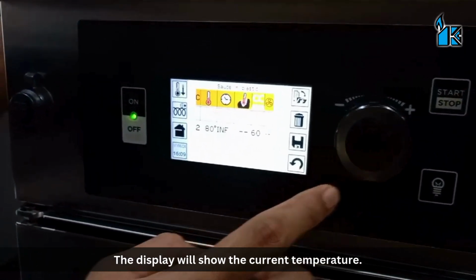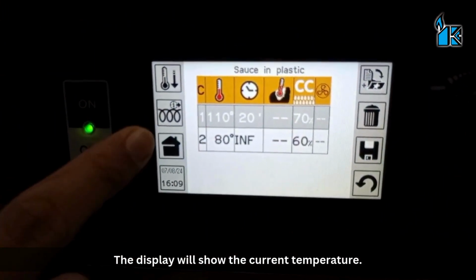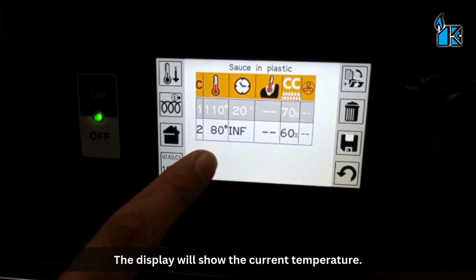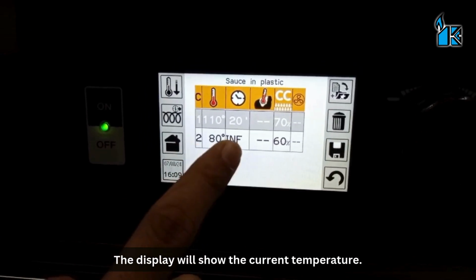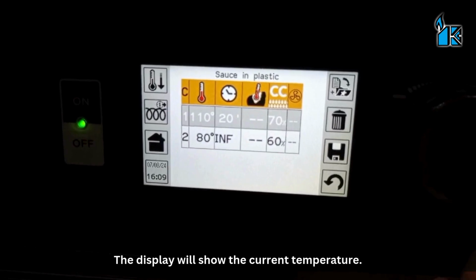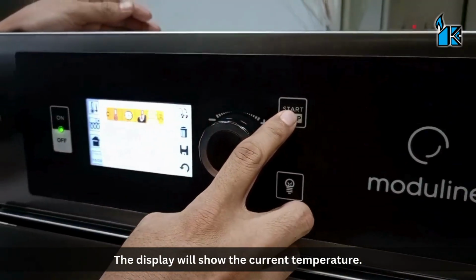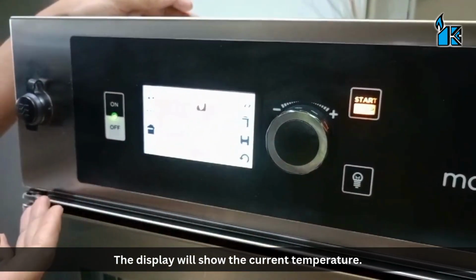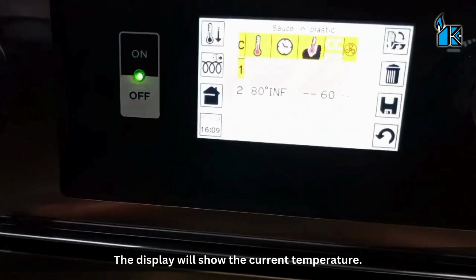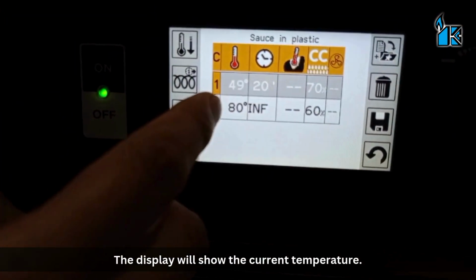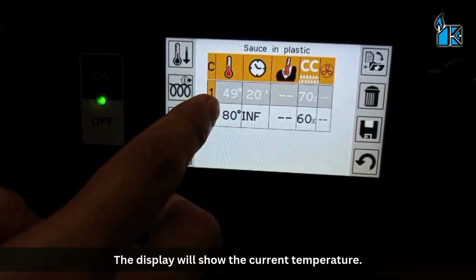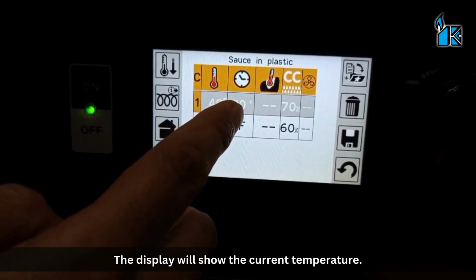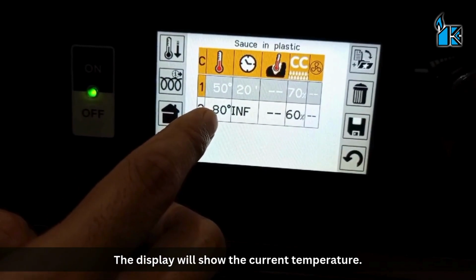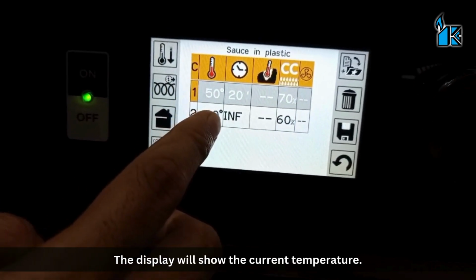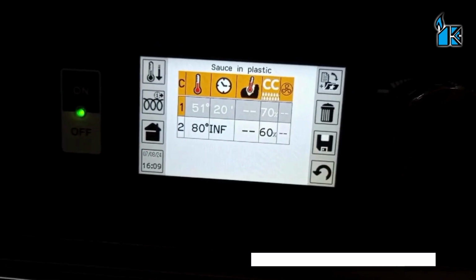The panel will show the setting we have done for regenerating the product. To start this, press start. This is a 2-cycle regeneration program. First cycle, it will regenerate up to 110 degrees for 20 minutes. Second cycle, it will maintain the temperature at 80 degrees for holding, infinitely.